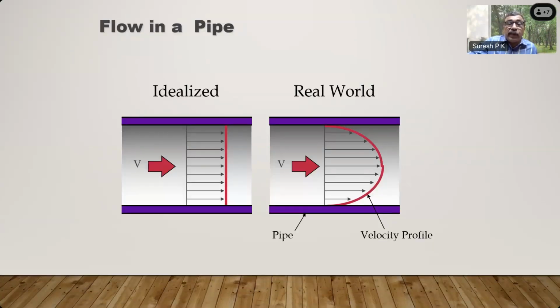The flow in a pipe, ideally, you would think has the same velocity from the wall to the center, and that is the velocity you are measuring. No, it's not. In the real world, the velocity is a curve. It's a velocity profile. If you measure velocities at various depths in a pipeline, they will be different. That is called the velocity profile, which is normal, not abnormal.